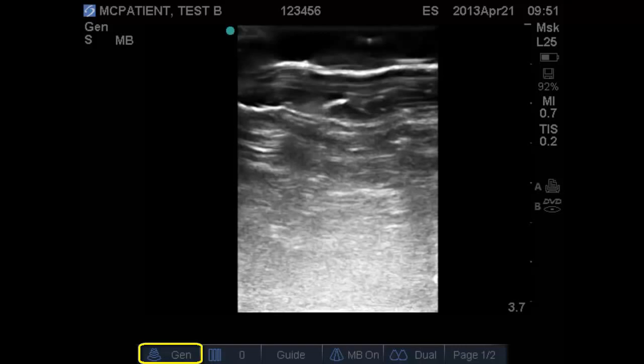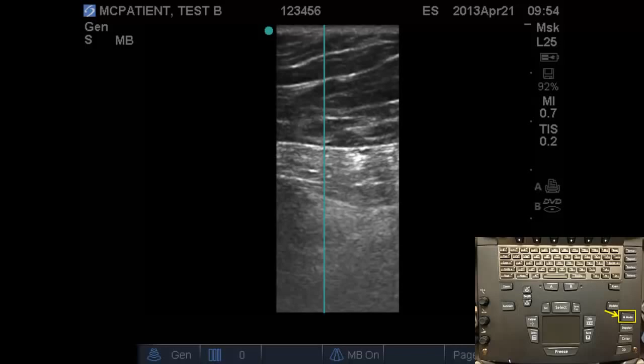M or motion mode takes a single cut of the ultrasound image over time. Press the M mode key once to bring up the sample line on the screen. The sample line can be moved to the target area using the trackpad. Once you have the sample line over the area of interest, press the M mode button again to see the tracing over time.